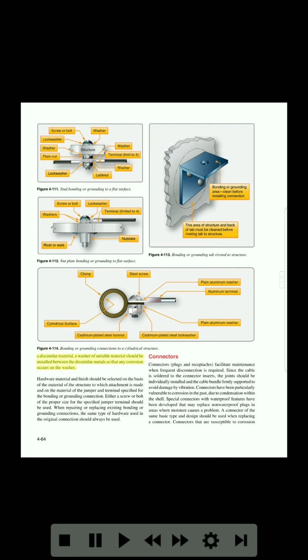A dissimilar material: a washer of suitable material should be installed between the dissimilar metals, so that any corrosion occurs on the washer. Hardware material and finish should be selected on the basis of the material of the structure to which attachment is made and on the material of the jumper and terminal specified for the bonding or grounding connection. Either a screw or bolt of the proper size for the specified jumper terminal should be used. When repairing or replacing existing bonding or grounding connections, the same type of hardware used in the original connection should always be used.